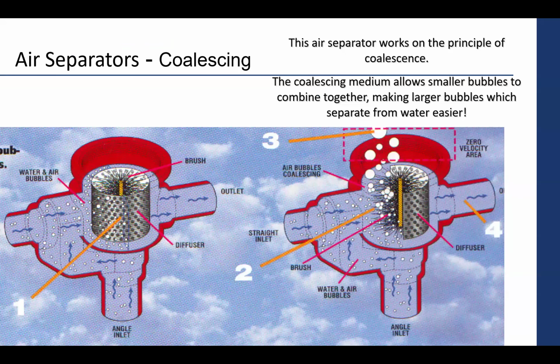The next one up, very popular in residential and light commercial, would be this coalescing type. What they're referring to is that the coalescing medium allows these smaller bubbles to combine. They gather. The velocity in that area and the surface area of these little stainless steel fingers allow the smaller bubbles to gather, and when enough of them gather together, it becomes a larger, more buoyant bubble that will then release and vent out through the vent located on the top of this device. So as the flow comes through with these bubbles, it gives them surface area to grab onto.